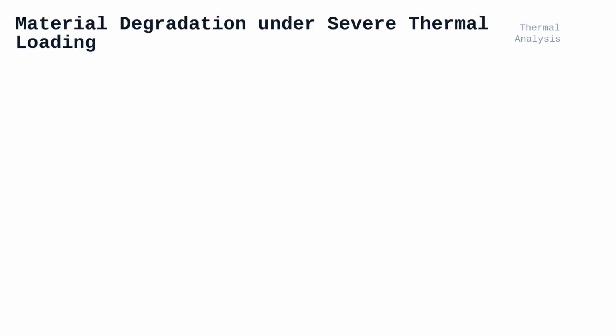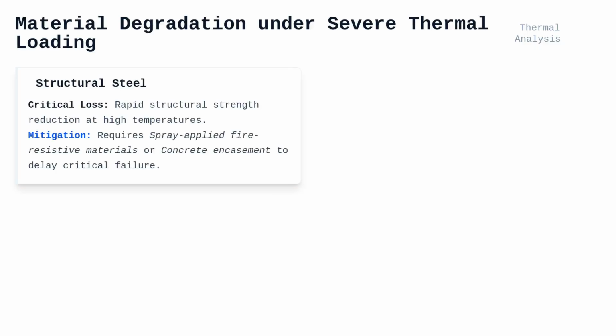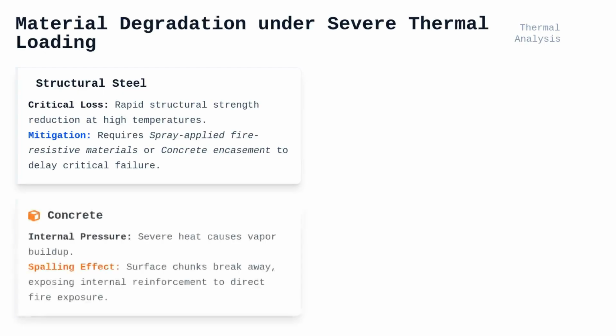The physics of material degradation under severe thermal loading is a critical area of study for the practicing professional, particularly regarding how different building materials respond when subject to intense heat. Steel, for instance, loses its structural strength quite rapidly as temperatures rise, typically reaching a critical temperature where it can no longer support its required design load, necessitating the use of spray-applied fire-resistive materials or concrete encasement to delay this outcome. Concrete behaves differently, often suffering from internal vapor pressure buildup that leads to spalling, a condition where chunks of concrete break away from the surface and expose the internal reinforcement to the fire.